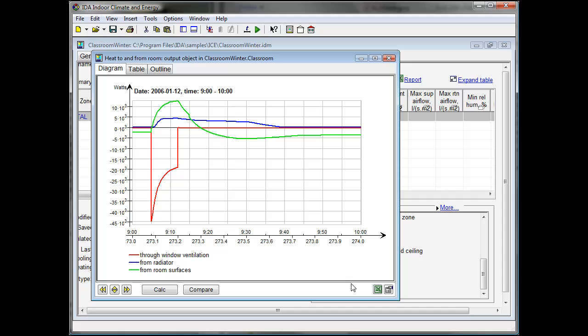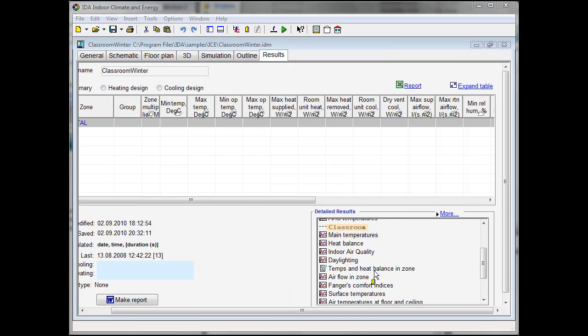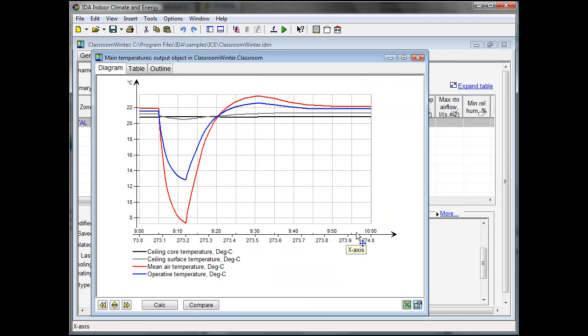We can also see the heat in green from wall surfaces to the classroom which can compensate already quite a big amount of this heat loss, and in blue the radiator power which is only 5 kW. But even with this low heating power, room temperatures get back to reasonable levels when pupils are reentering the classroom.